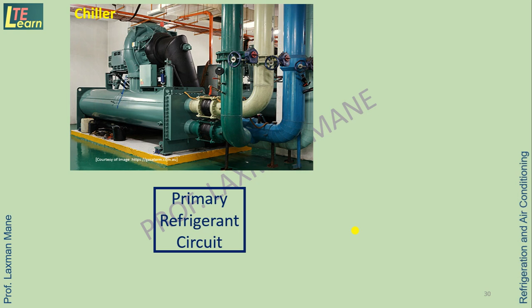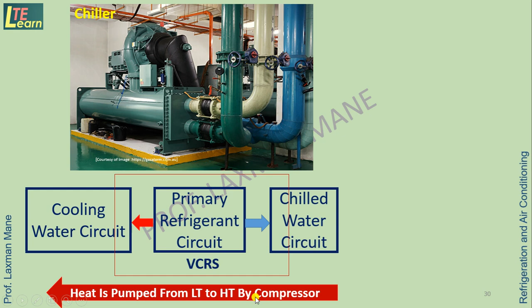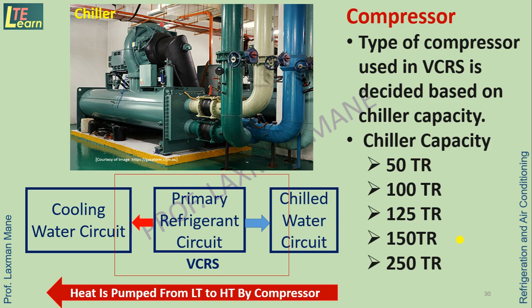So here, heat from the chilled water circuit is absorbed by the primary refrigerant and is rejected to the cooling water circuit. So in this chiller and vapor compression refrigeration system, heat is pumped from low temperature to high temperature by using a mechanical device, a compressor. The type of compressor used in the vapor compression refrigeration system is decided based on chiller capacity. Chiller capacity is in the range of 50 TR to 250 TR as shown here.